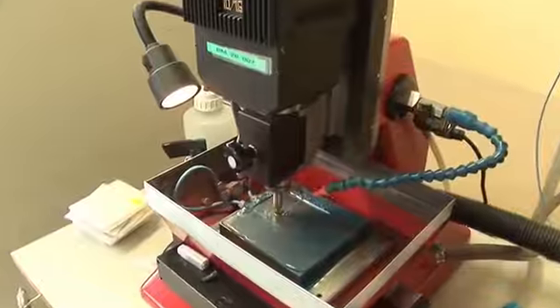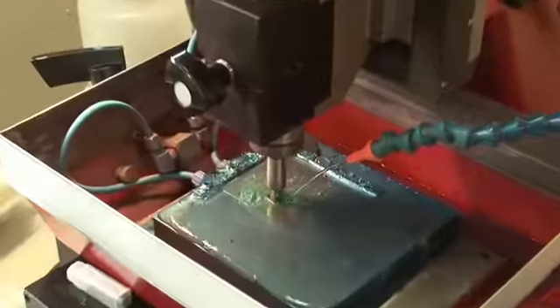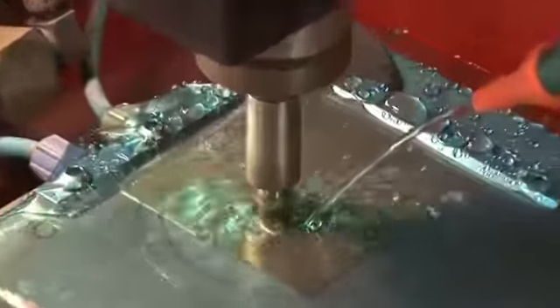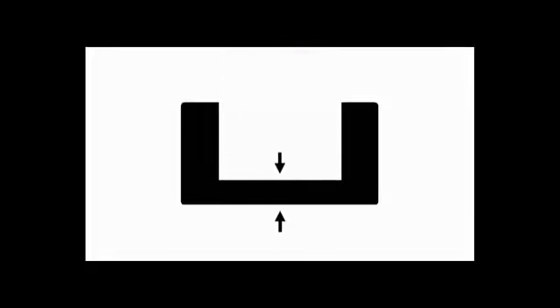In the first production stage, the transducer's sensitivity, essentially the pressure range that it will measure, is defined. This is done by drilling a hole on the back of the silicon chip. More or less silicon is drilled out depending on the desired pressure range of the sensor.